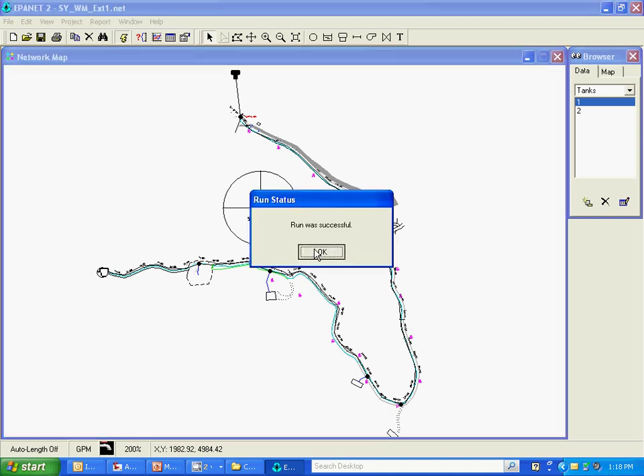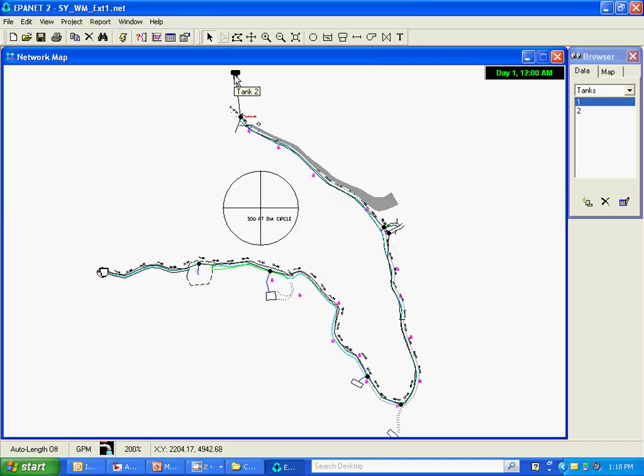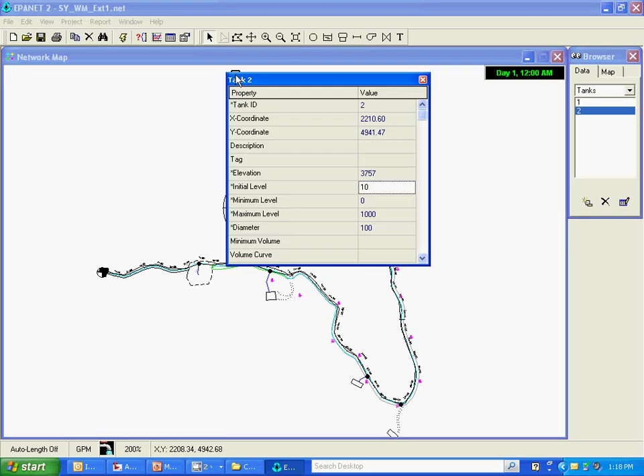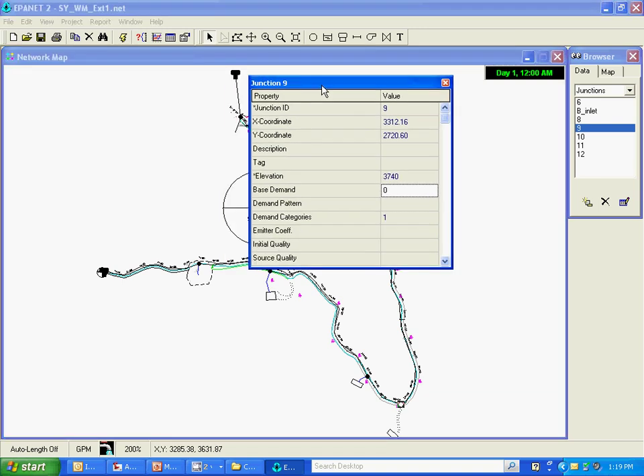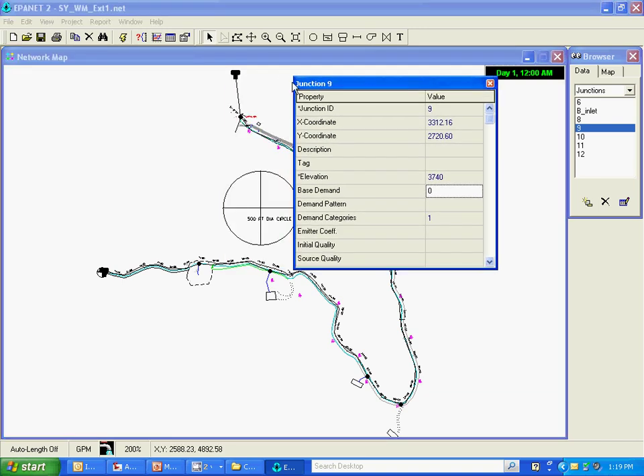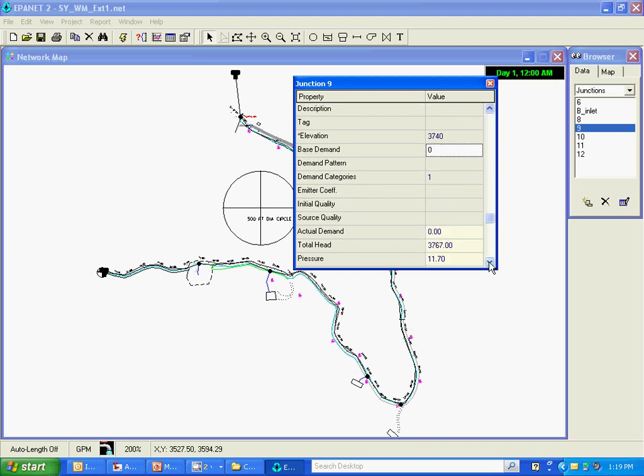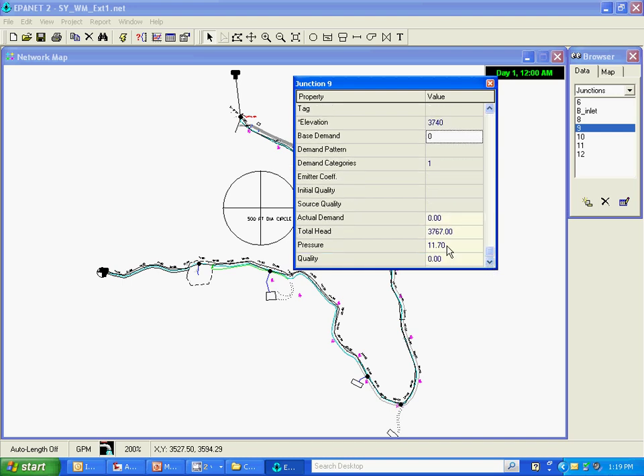It's telling me the run was successful. I'm going to take a look at the elevation of this tank, which is 3757. It's also got a water level of 10 feet, so the total liquid level in that tank is 3767. The elevation of this node down here is 3740, so the elevation difference between this tank and this node should result in the pressure at that node. And the model does list the pressure at 11.7 psi.